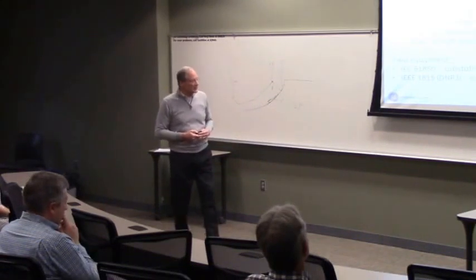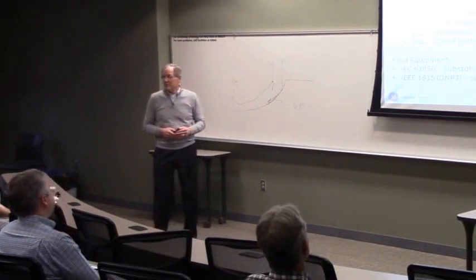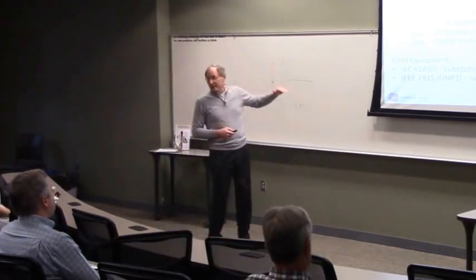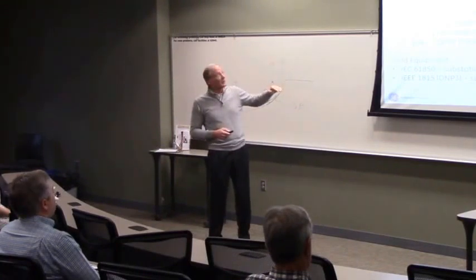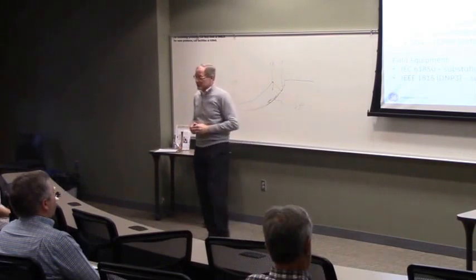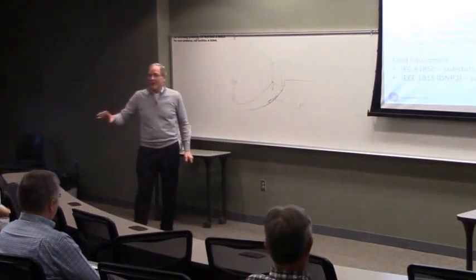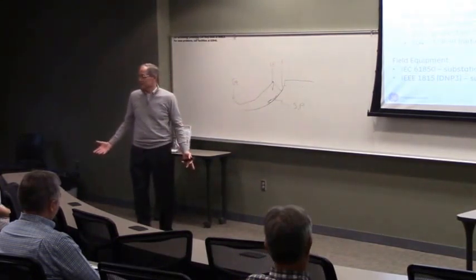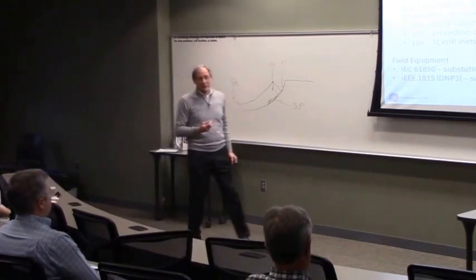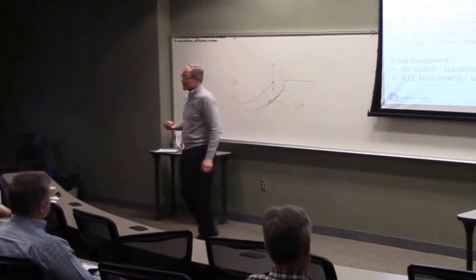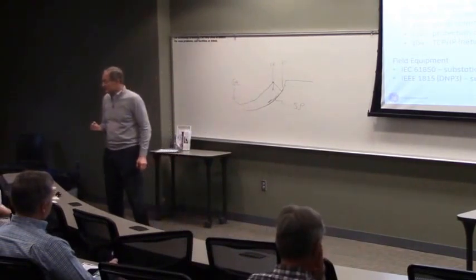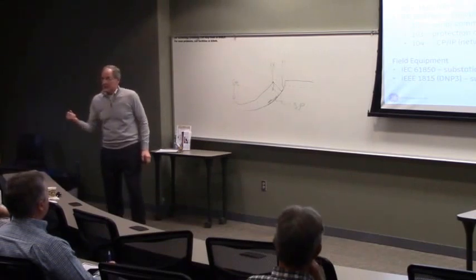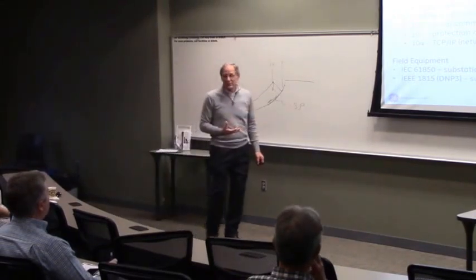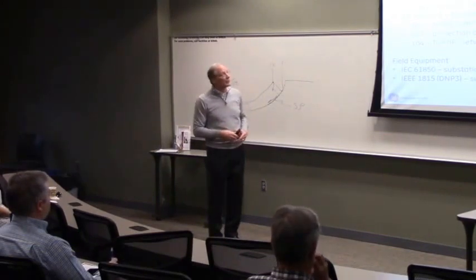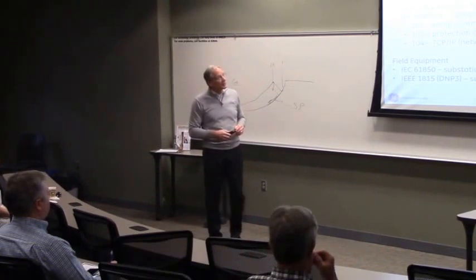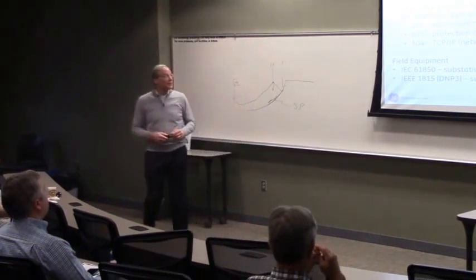And again, what's nice today around the world is if we look at 3 different levels of the grid in the architecture. At the top level, we're control center to control center. So you're at PPL, and you want to communicate information to PJM. Or your EMS for generation and transmission needs to communicate information to your DMS. You have a DMS for distribution, EMS for generation and transmission. The worldwide standard today for that control center to control center communication is what we call ICCP, Inter-Control Center Communications Protocol, or IEC 870-6.